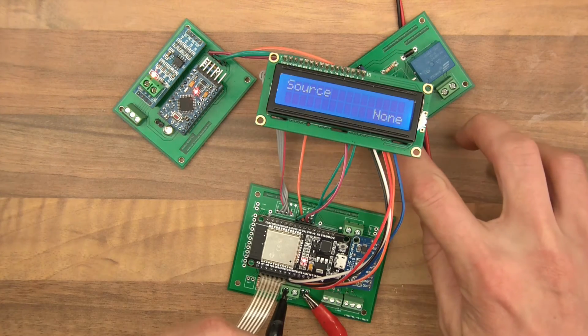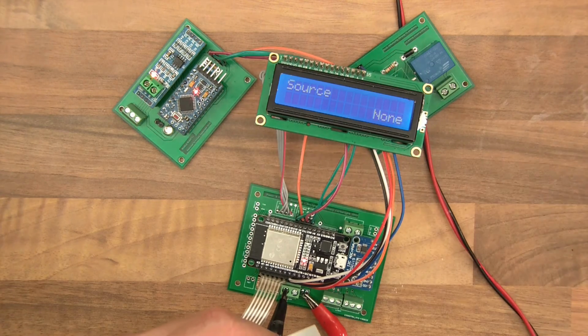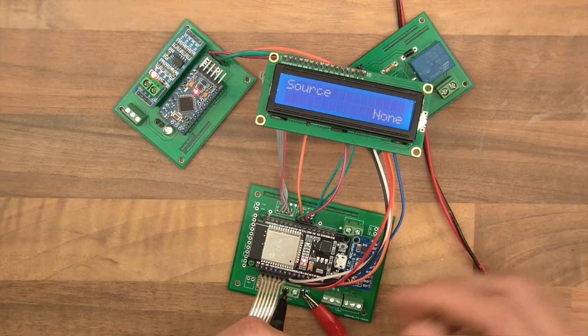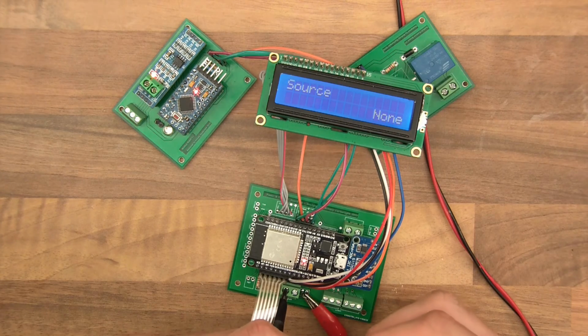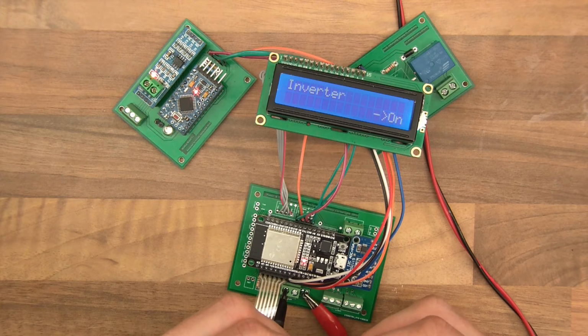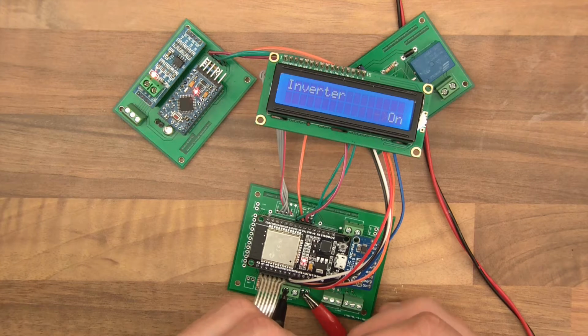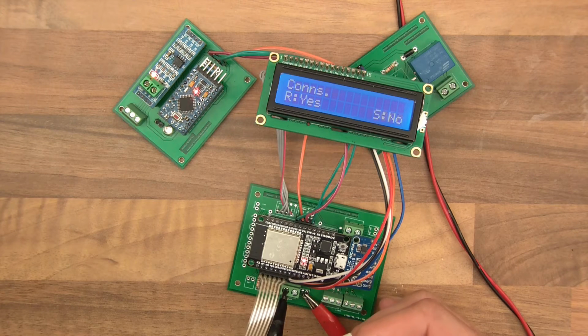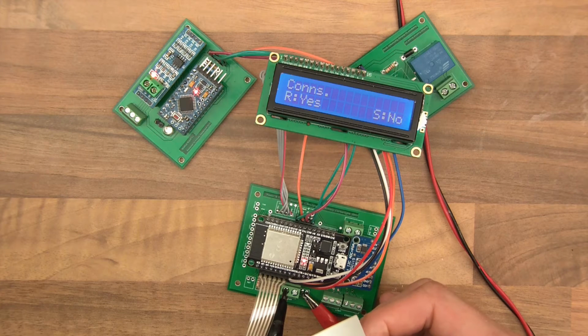One of these transistors down here should have changed over, because the transistors power the contactors. Now the inverter, we want to switch it off, and now the relay should click. Yeah, you heard it click. Let's turn it back on. Should click again. Yep, so that's working fine. Turn it back off again. I'm going to go back to those menus in a minute and test with the ohmmeter.